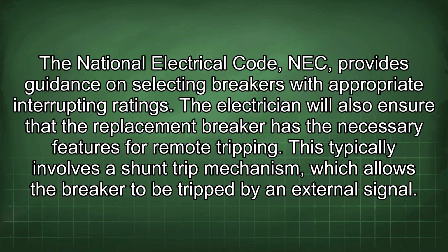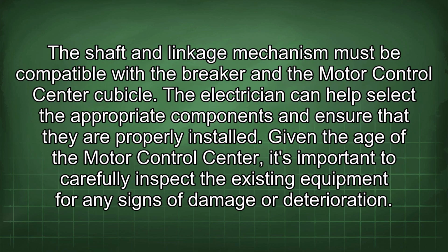The electrician will also ensure that the replacement breaker has the necessary features for remote tripping. This typically involves a shunt trip mechanism, which allows the breaker to be tripped by an external signal. The shaft and linkage mechanism must be compatible with the breaker and the motor control center cubicle. The electrician can help select the appropriate components and ensure that they are properly installed.